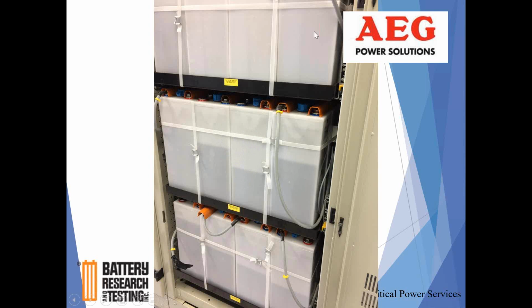But back to these sensors. These sensors are notorious for falling off of the side of the jar, and there's a very particular way that they need to be reinstalled. So a lot of people just try to tape them from the back onto the jar. The alarm stays active. They get frustrated. They just kind of coil the sensor up, lay it in the bottom of the cabinet, and put a tag on the outside.